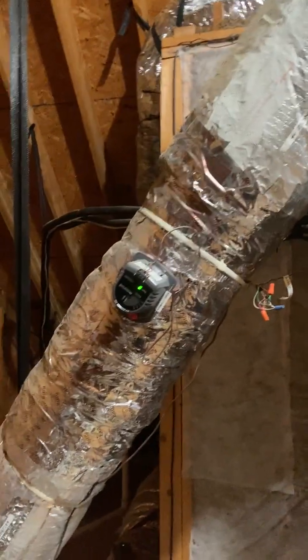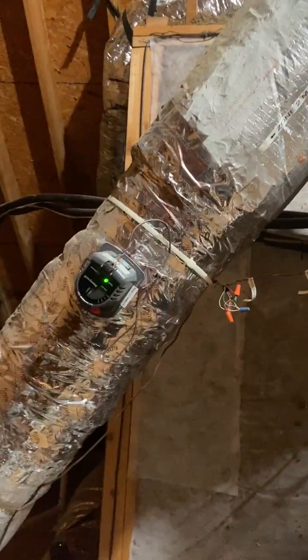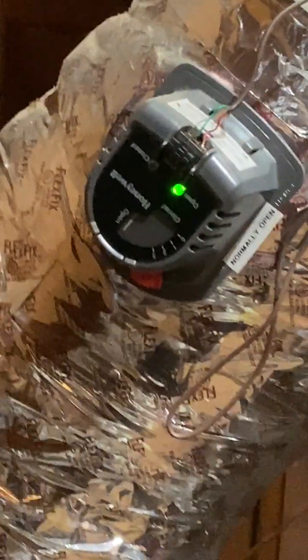This is the zone control valve for what I call zone 2, and it is a newer Honeywell type zone control valve. Here it is, and it shows it's currently open, and that is a normal position that the valves are in. And here's the wiring for it coming down. It has 3 wires. You really only need 2, but the 3rd wire allows that light to go from green when it's open to red when it's closed.